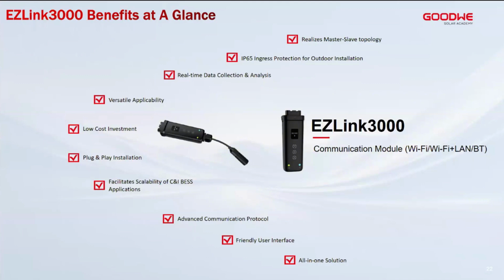From 2 to 4 inverters, you can use the EasyLink module to establish the master-slave. One of the inverters becomes the master, and the rest report to the master so that the whole system works as one. The product itself is IP65, so just like the inverter, you can install the communication module outdoor as well. The product allows real-time data collection and analysis: using Wi-Fi or the LAN cable, you connect the product to the internet, and the data from the inverter is uploaded to the GoodWe monitoring portal, which is called the SEMS portal.